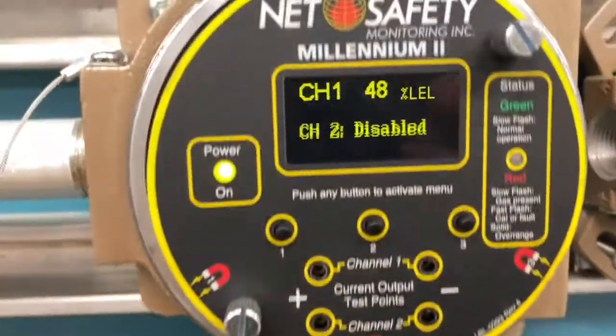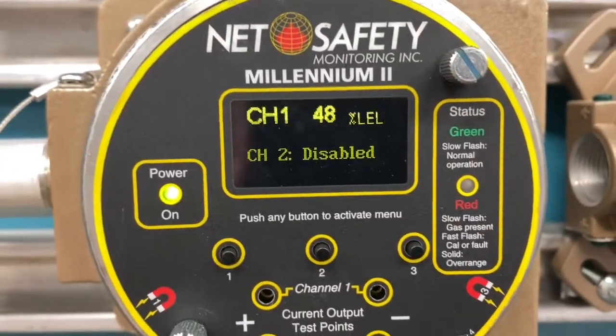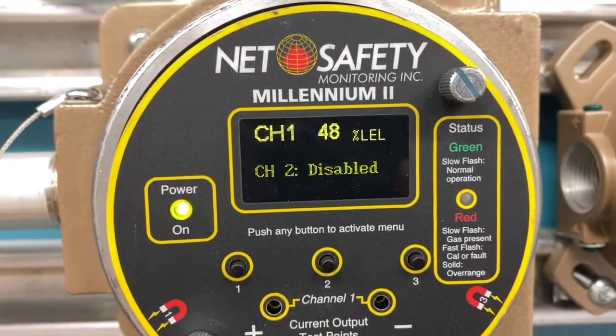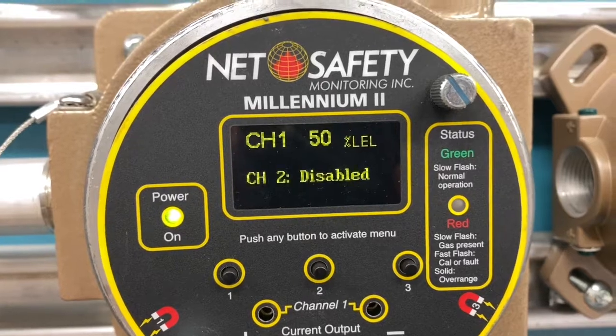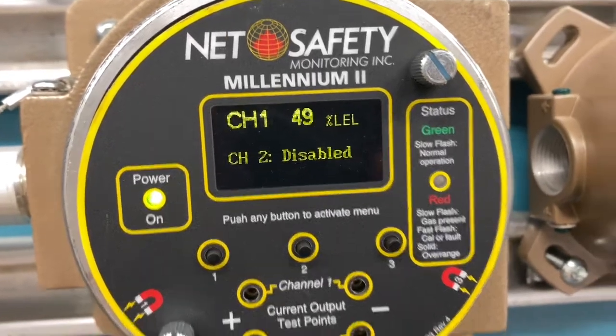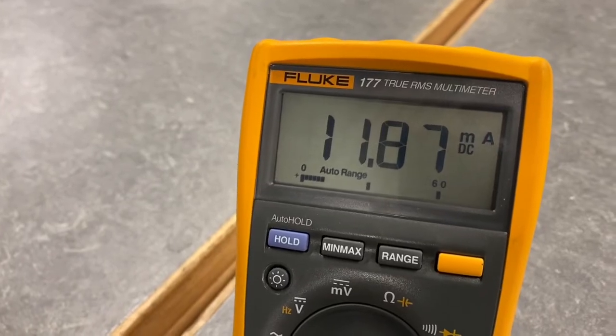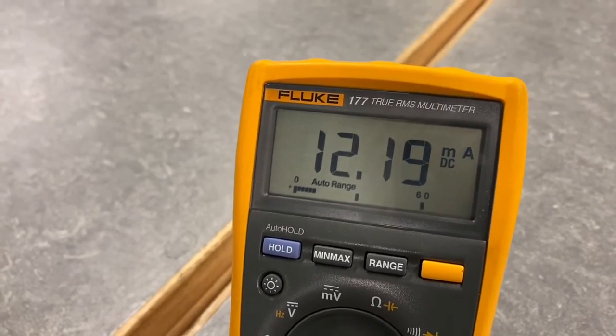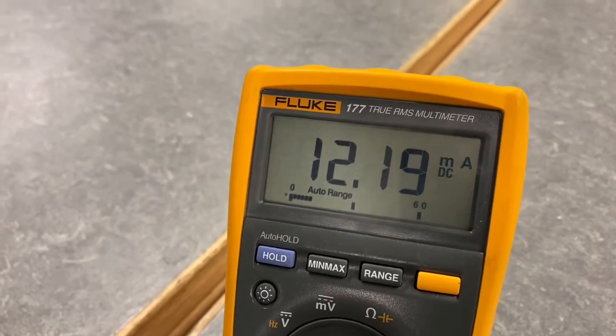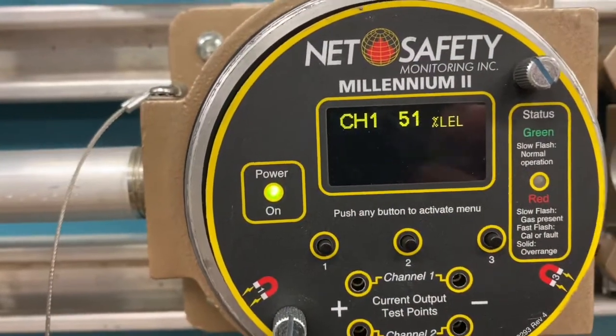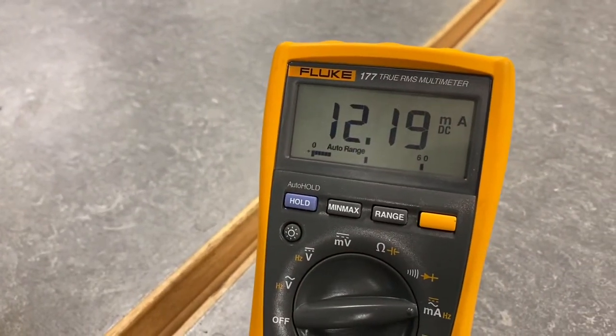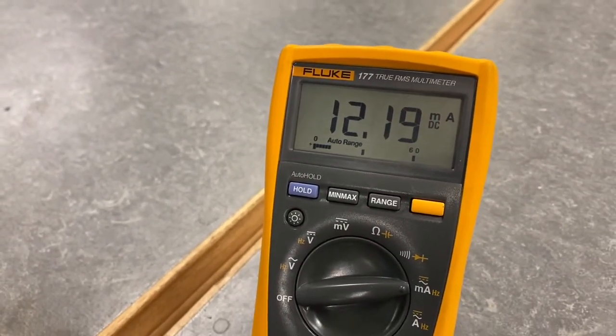At 48% LEL, we'll see if it gets up to 50. There we go, looks like we've hit 50% LEL, and we're reading pretty close to 12 milliamps. It's bouncing between 12 and, yeah, so we must be at 50% LEL, 51% LEL. It looks like it's reading pretty close. Everything's good there.